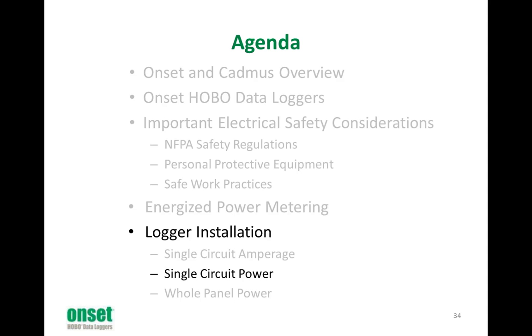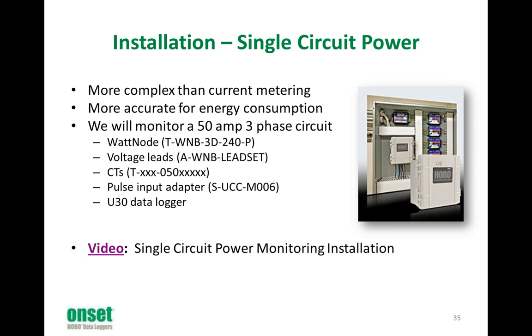We'll now look at logging single circuit power, and we'll do that with a Wattnode and a U30. This is more complex than current metering, so we're looking at true power. Basically, the Wattnode is a kilowatt-hour transducer, and we can also derive kilowatts from that. For the example we're going to see in the video, we monitor a 50-amp three-phase circuit. The part numbers are a Wattnode TWNB-3D-240-P for pulse output. We use a voltage lead set provided from Onset Computer Corporation. That's the A-WNB lead set. I'll discuss that a little bit more in the video.